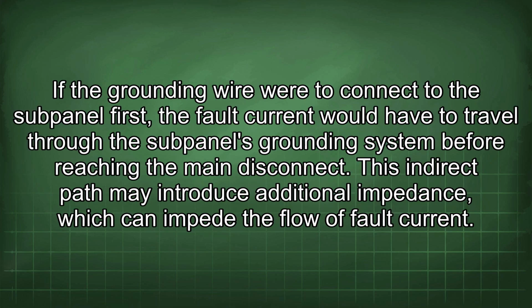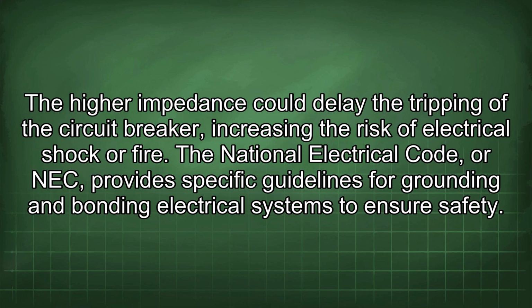If the grounding wire were to connect to the subpanel first, the fault current would have to travel through the subpanel's grounding system before reaching the main disconnect. This indirect path may introduce additional impedance, which can impede the flow of fault current. The higher impedance could delay the tripping of the circuit breaker, increasing the risk of electrical shock or fire.